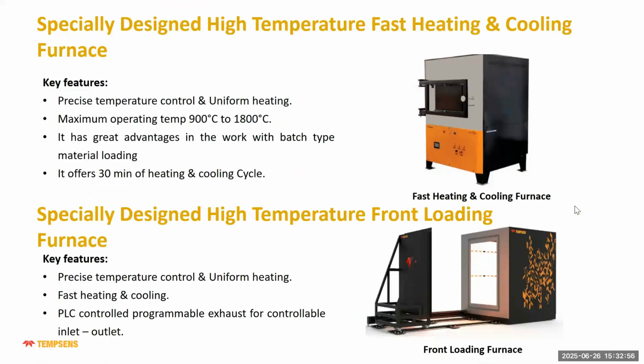These are specially designed high temperature fast heating and cooling furnaces. If there is a requirement of very fast heating and very fast cooling, we can give a special system in which the heating element can be silicon carbide, which can heat the material inside 30 minutes, and then also cool the material from 1200 to 600 degrees centigrade in 30 minutes by using forced air circulation. We purge outside air inside the furnace, and there will be an exhaust fan on the outside. It will extract the heat from inside the furnace, and it will cool fast. So it offers a 30 minute heating and cooling cycle. We can also provide a front loading furnace with very big sizes, around 1 meter by 1 meter by 1 meter for 1800 degrees centigrade.